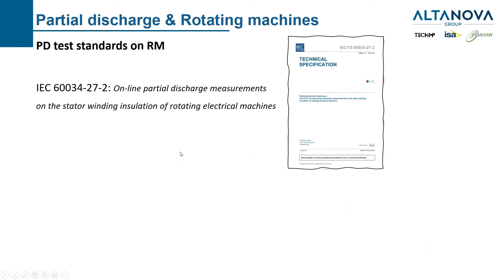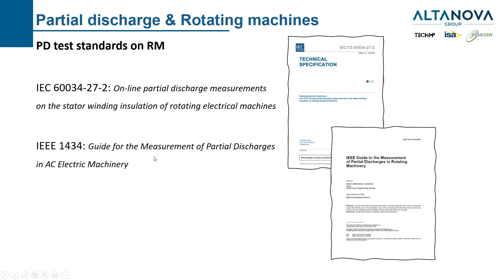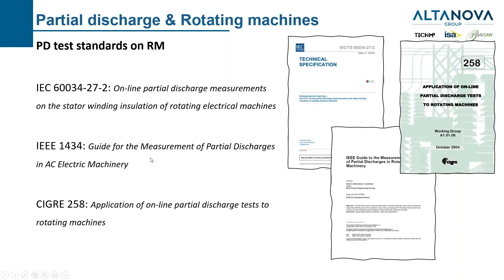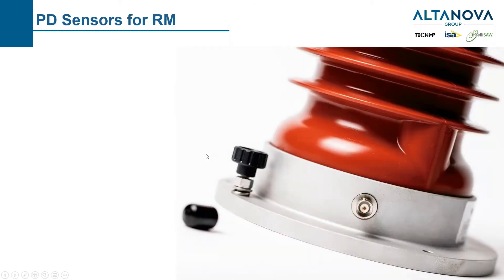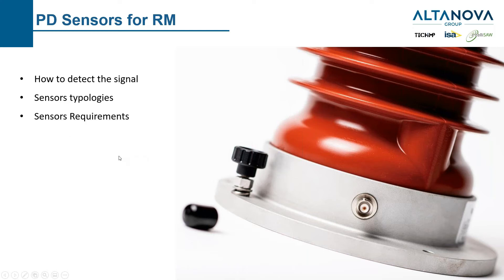In literature we can find some guides and standards for rotating machine testing. We have for example IEC 60034-27 part 2, related to online partial discharge measurement. We have the IEEE 1434, and we also have the CIGRE 258 with application of online PD tests to rotating machines. Now, what can we say about the sensors used to record partial discharge in rotating machines? We will see how we detect the signal, the sensor typologies, the requirements of such sensors, and the positioning of the sensor, signal handling, and safety.